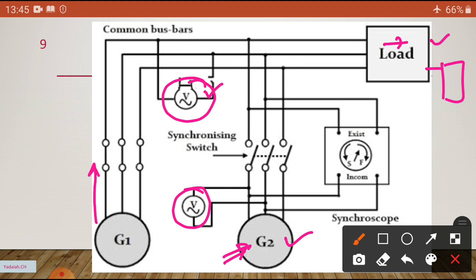So V1 is equal to V2 in magnitude. At the same time, I want to check the phase also. With the help of the voltmeter, this voltage generates 11 kV, and this also generates 11 kV. If it is not equal, we can adjust the speed or fuel or everything. Now the first point is satisfied.